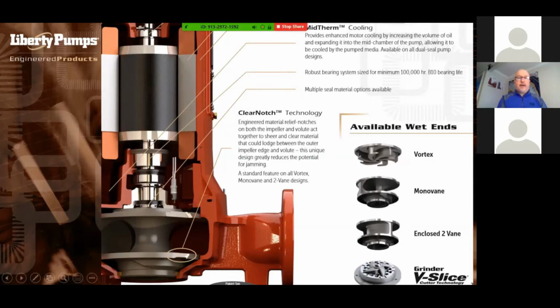Another patent pending feature we added is this clear notch design, clear notch technology. These are relief notches, as we call them, but basically they're grooves that we cut into the top and the bottom shroud of the impeller, and also a groove or a ramp we cut into the volute. The reason we did this is we tested a lot of different pump manufacturers pumping wipes and rags and fibrous material. After going through some of that material, we took the pump apart and looked at it. Some of that material would get wedged between the impeller and the volute and either slow it down or cause it to jam and stop the pump. So we came up with this clear notch design that gives it an area to clear itself out but also shears the material at the same time to cut it so it can make its way out and not get lodged between the impeller and the volute.